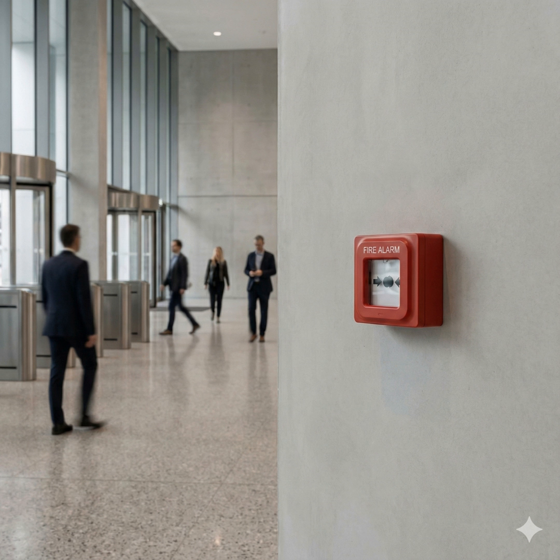Let's directly address that analyst's concern. False alarm reduction. Chronic false alarms are more than just a nuisance. They create occupant complacency. And you can't ignore the human psychology. If people hear the alarm weekly because of, say, burnt toast, they will hesitate during a real emergency. Reduction requires detailed analysis of what's causing the nuisance and then careful sensitivity calibration for that specific environment.